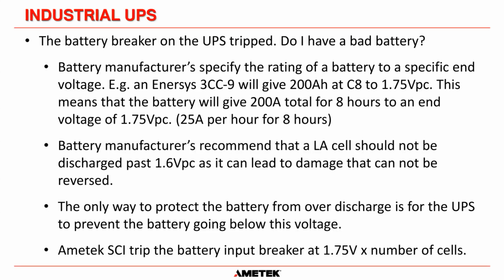It will give you 200 ampere hours at the C8 rating, so 200 ampere hours for 8 hours down to 1.75 volts per cell. This means that the battery will give you a total of 200 amp hours to an end voltage of 1.75, which means you divide that 200 by the 8 hours, and you will get 25 amps for 8 hours until the battery will then, by design, go down to about 1.75 volts per cell. So that's the first thing you need to understand.